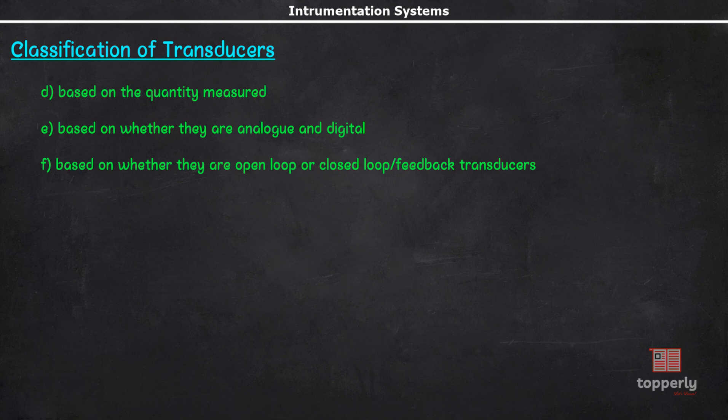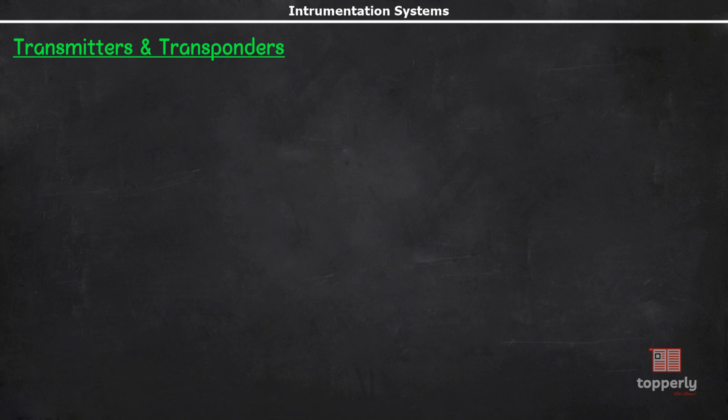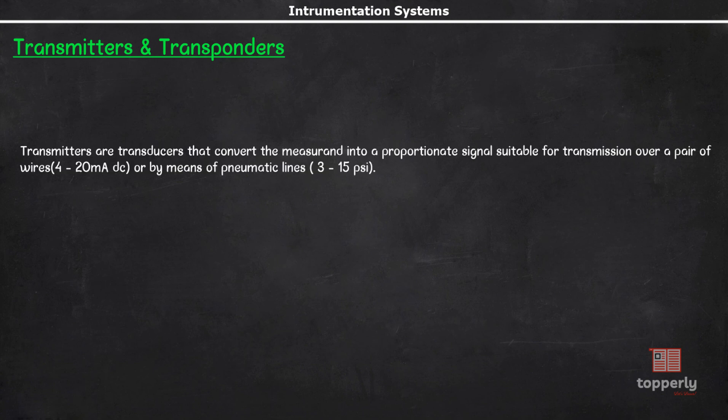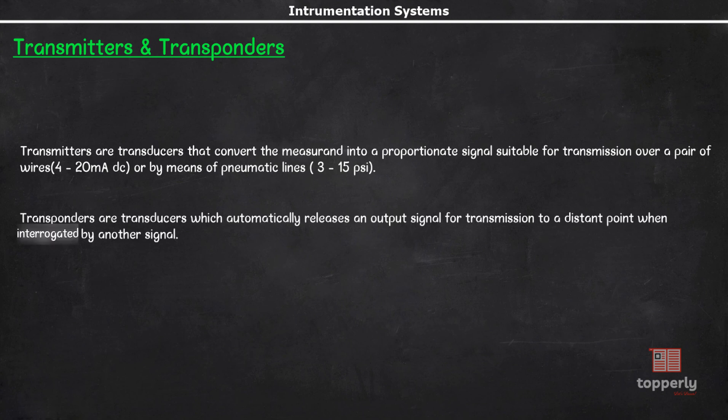Now, there are two terminologies that come under the topic of transducers which you should be familiar with. They are transmitters and transponders. Transmitters are transducers that convert the measurand into a proportionate signal suitable for transmission over a pair of wires or by means of pneumatic lines. Meanwhile, transponders are transducers which automatically release an output signal for transmission to a distant point when interrogated by another signal. An example is an RFID device which transmits a coded signal when it receives a request from a monitoring or control point.